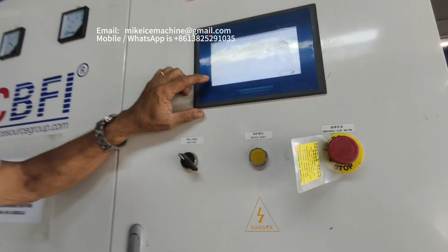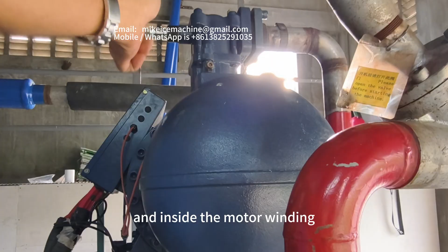This is the last recorded problem, around November 14, 2023. And the indication says compressor protect. This signal came from the exhaust valve, this one, and inside the motor winding. That is the one that gives the signal to trip the system. And is that the error we were facing all the time? Yeah, all the time after 9,000 hours. So the original problem is oil. Yeah, we all know, without good oil quality, a machine can never really work.